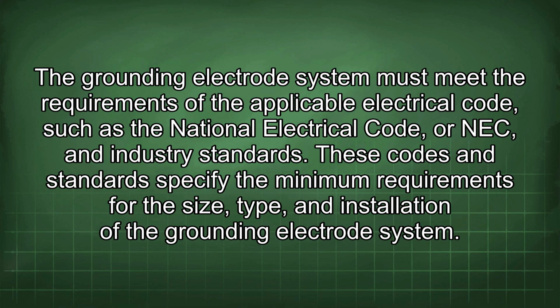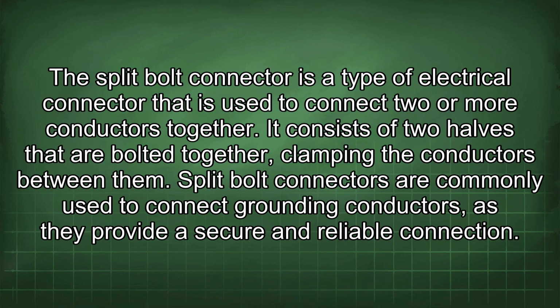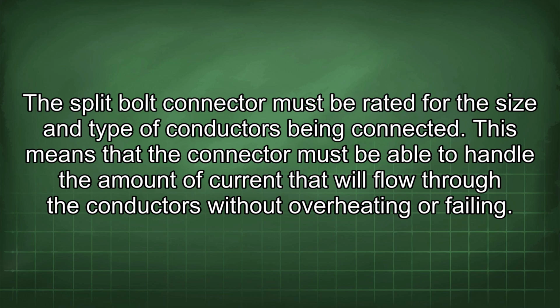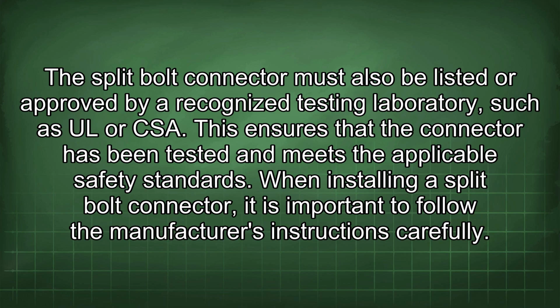grounding electrode system. The split bolt connector is a type of electrical connector that is used to connect 2 or more conductors together. It consists of 2 halves that are bolted together, clamping the conductors between them. Split bolt connectors are commonly used to connect grounding conductors, as they provide a secure and reliable connection. The split bolt connector must be rated for the size and type of conductors being connected. This means that the connector must be able to handle the amount of current that will flow through the conductors without overheating or failing. The split bolt connector must also be listed or approved by a recognized testing laboratory such as UL or CSA. This ensures that the connector has been tested and meets the applicable safety standards.